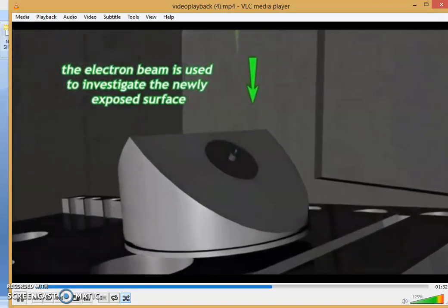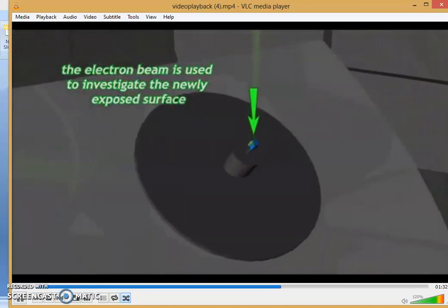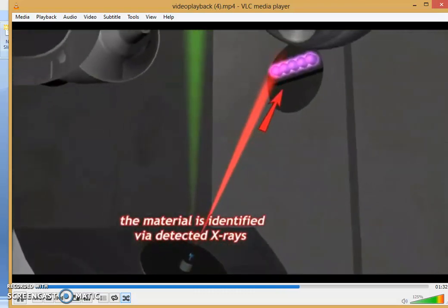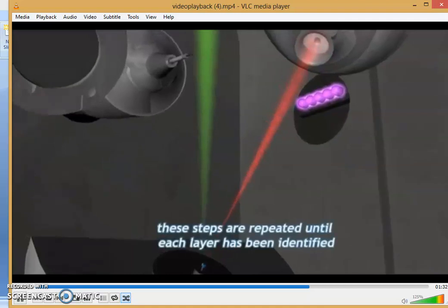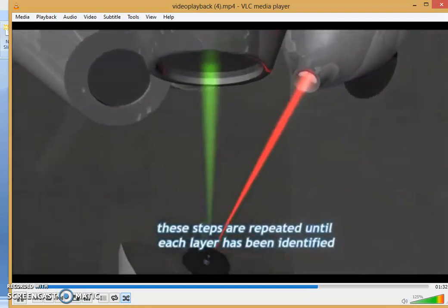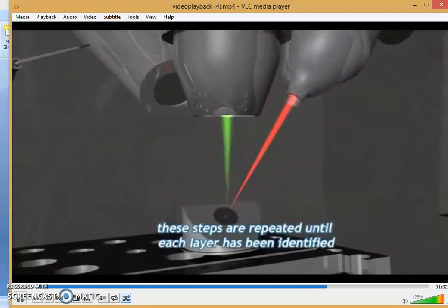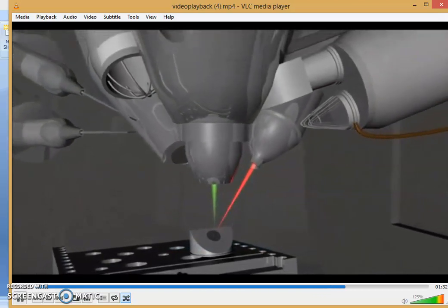Means this machine is a combination of the ion beam FIB process plus the electron microscope process, SEM process. Main function of a FIB: the ion beam is incident for machining purpose and the electron beam is incident for scanning to identify whether the level is achieved or not.